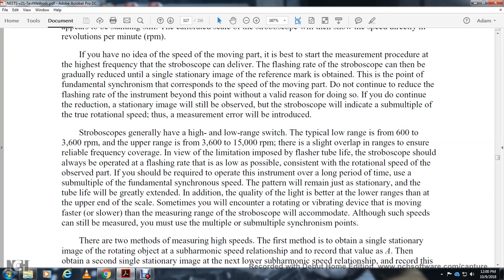Stroboscopes generally have high and low range switches, with a typical low range of 600 to 3,600 RPM and an upper range of 3,600 to 15,000 RPM, with a slight overlap in the range of the instrument. The reliable frequency is limited by the flashlight flasher tube. A stroboscope should always be operated with the flashing rate as low as possible, consistent with the rotation speed being observed. If it is required that you operate the instrument for a long period of time, use the submultiple of the fundamental synchronizing speed.